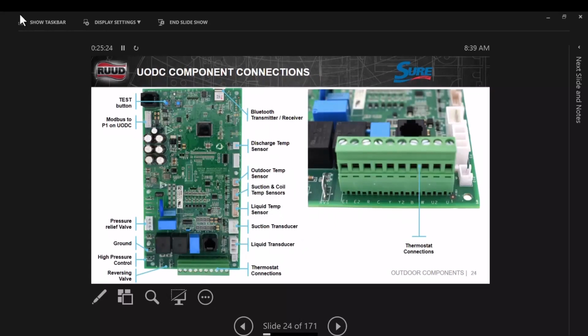This terminal block will come off, but you notice all the writings here, so just be advised that when you pull this off, you want to make sure of the orientation so we know what each terminal is. So right now, if you pull that thing off, make sure we're putting everything in the right place. Now, the only thing you're going to have going to this outdoor unit is going to be E1 and E2 and R and C. You got 4 wires going out there.